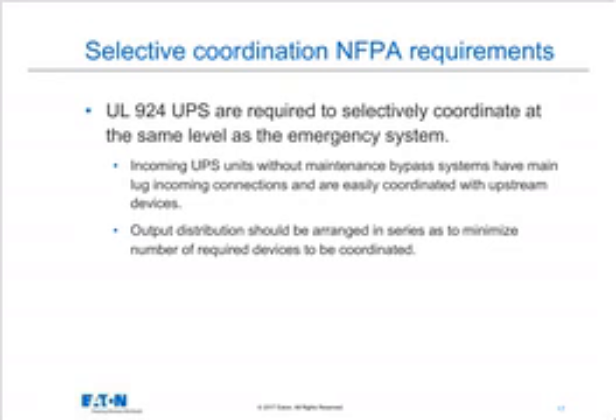So I need to perform selective coordination on those breakers upstream of the UPS and between the UPS and the distribution. And if the UPS transfers to plain utility power on an overload or failure, then the downstream distribution needs to be coordinated with the utility breakers that are associated with the UPS. This is not an option. Until relatively recently, it was not a requirement to coordinate here. But for safety reasons, I do not want a fault or a short circuit downstream in the distribution to cause a main breaker to open that dumps all the emergency lighting in that part of the building. That, of course, would be a disaster. So I do have to selectively coordinate the circuit breakers and or fuses and protective devices that are in line with the critical lighting devices that I'm supporting.